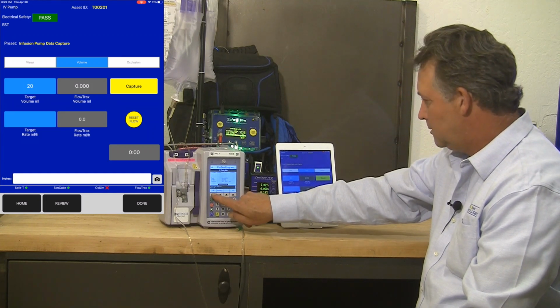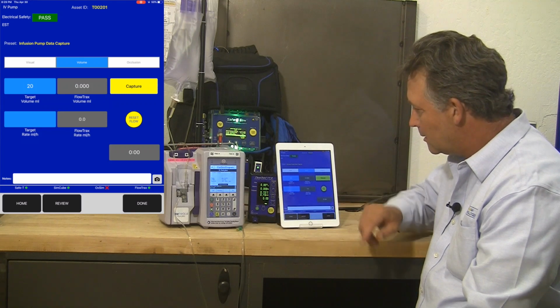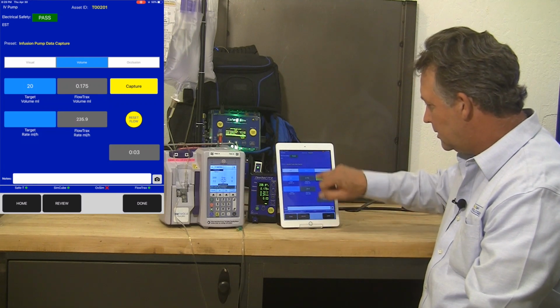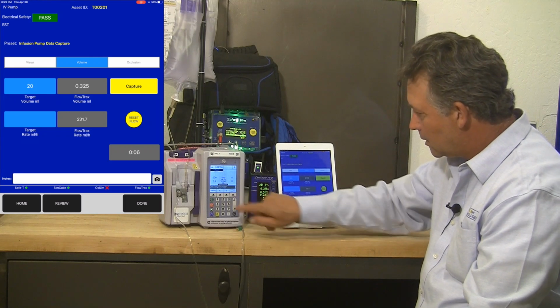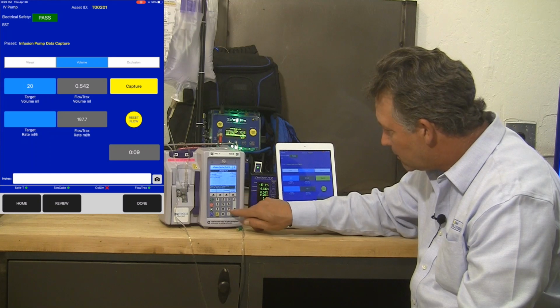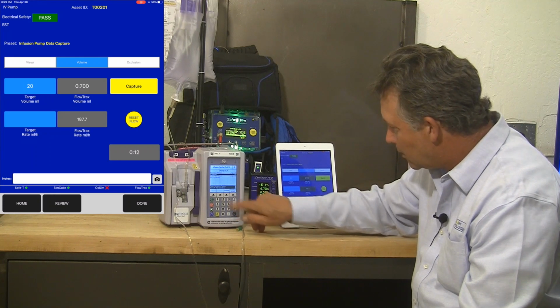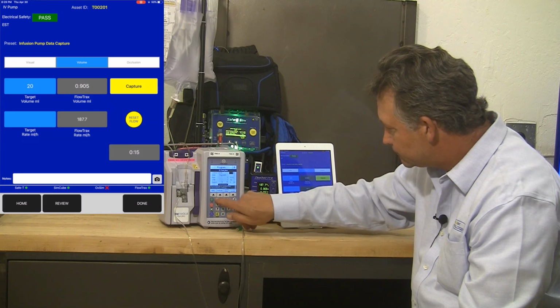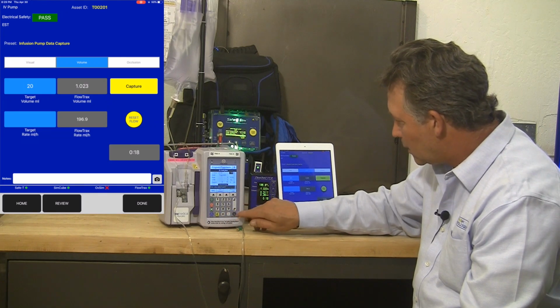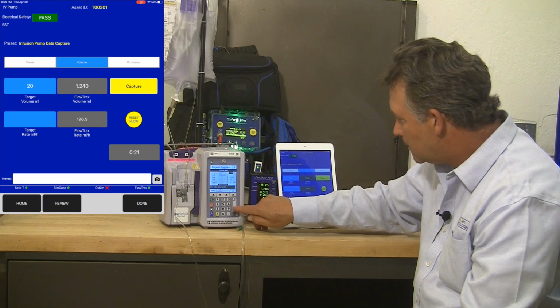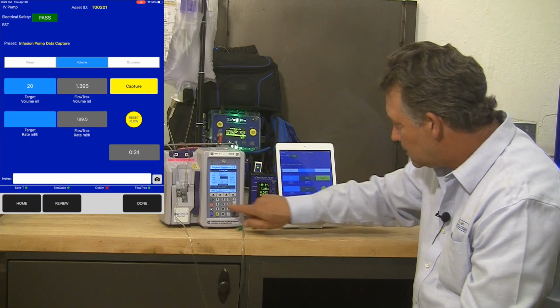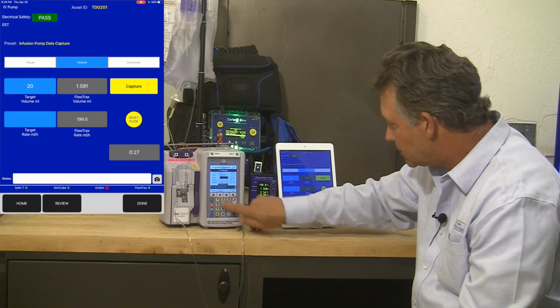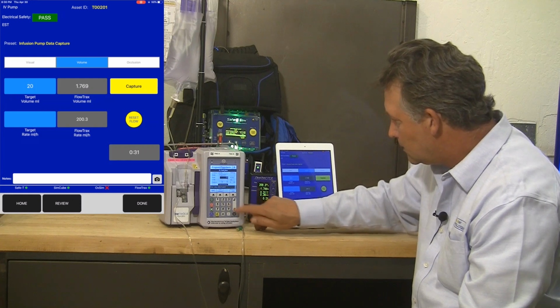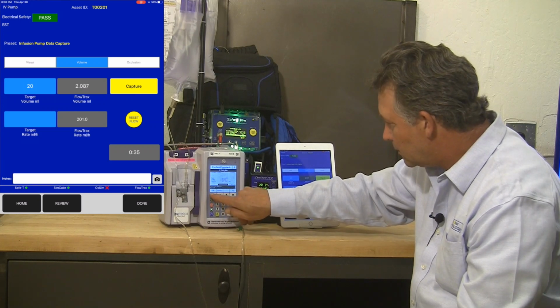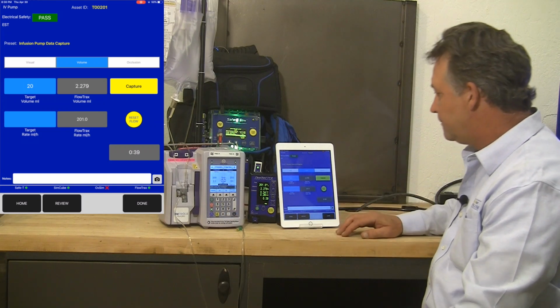Per the manufacturer process, I'm going to go ahead and start channel A, and we'll see that the results are already starting to get captured. While I'm doing that, I'm going to program channel B for the same rate and volume. All the while, the FlowTrax is capturing the rate and volume for channel A until I switch over. So I'm doing 200 milliliters per hour for a rate and 20 milliliters for this channel as well. Start to confirm, hit yes, and we're off and running.